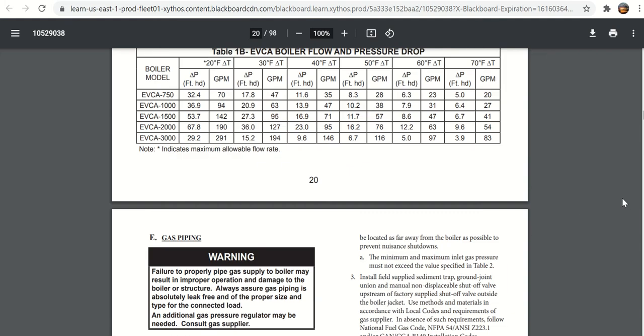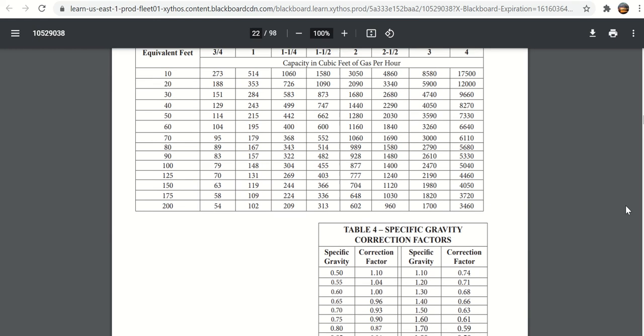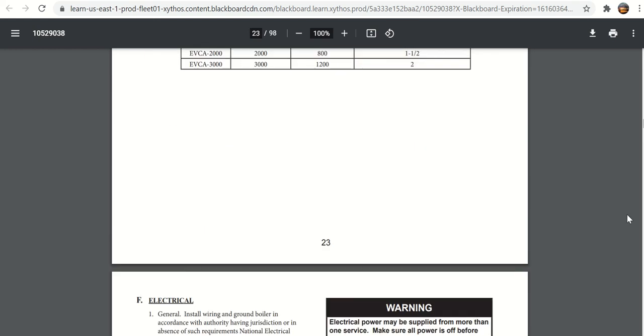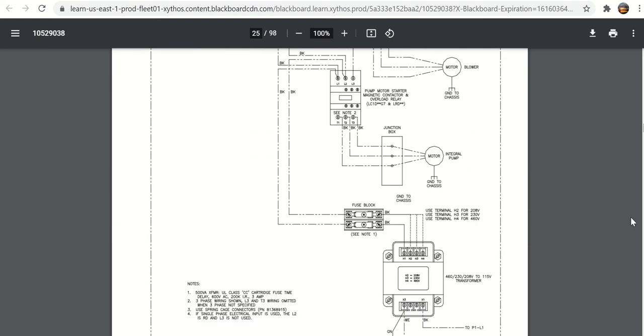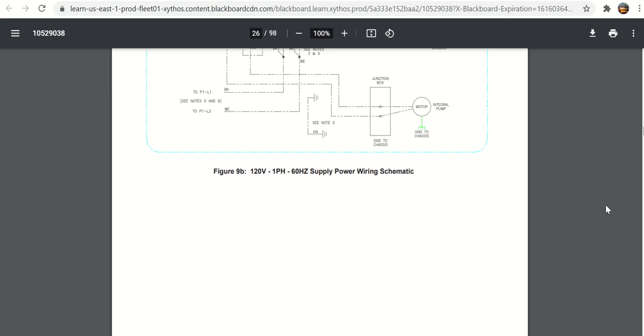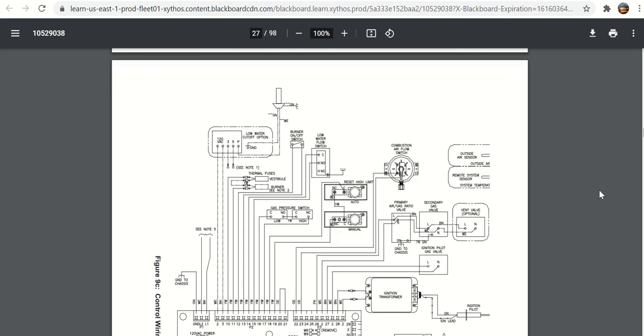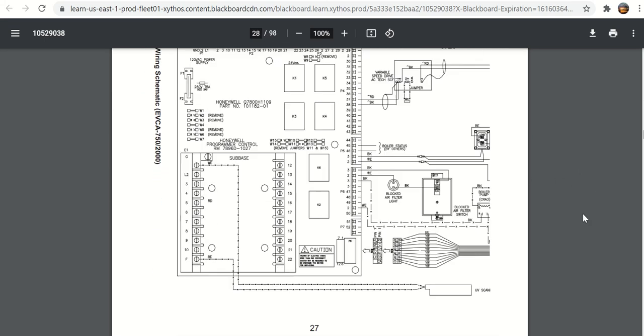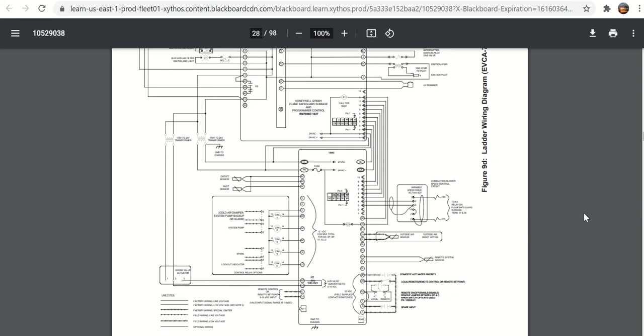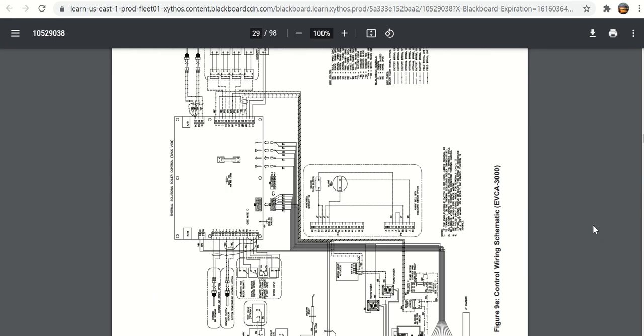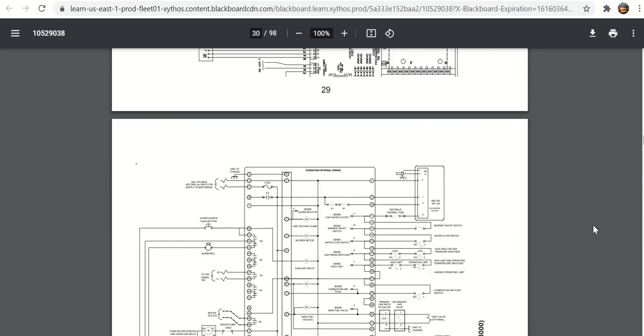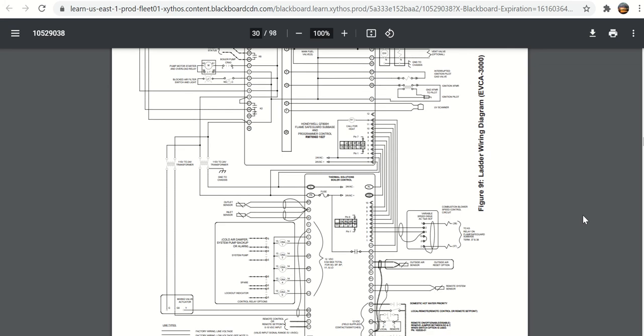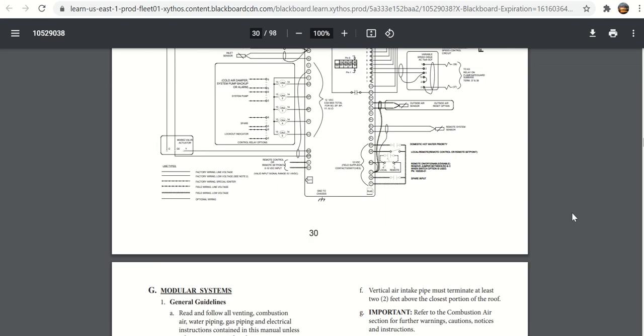One thing I was looking for in this literature, and I did not find it, and I'm not really sure why Thermal Solutions doesn't give you information like what type of thermistors they use. You know, they show in their diagrams, and there's some more pictures of the diagrams in the operation manual, but it doesn't necessarily tell you that it's a 10K type 2 or 1,000 ohm type thermistor. It just doesn't really tell you that. It just shows you that there's a remote system sensor or an outdoor temperature sensor.